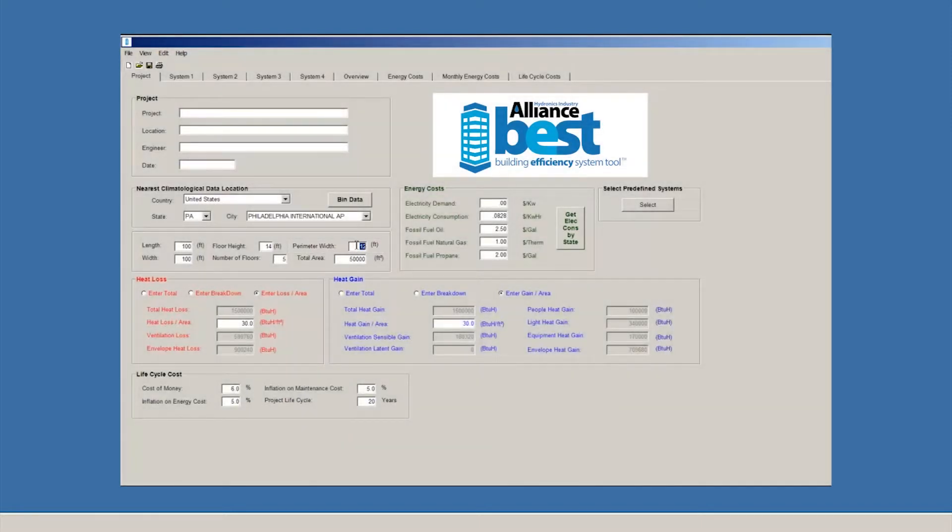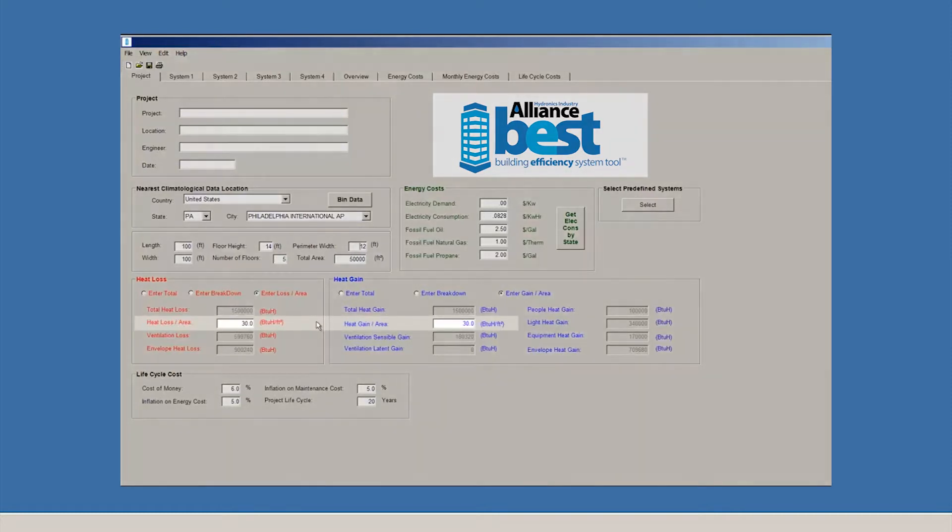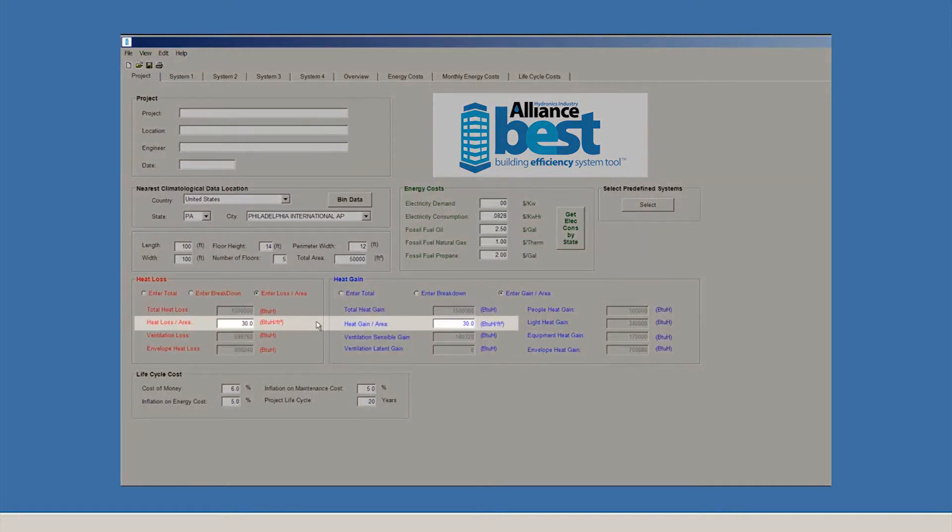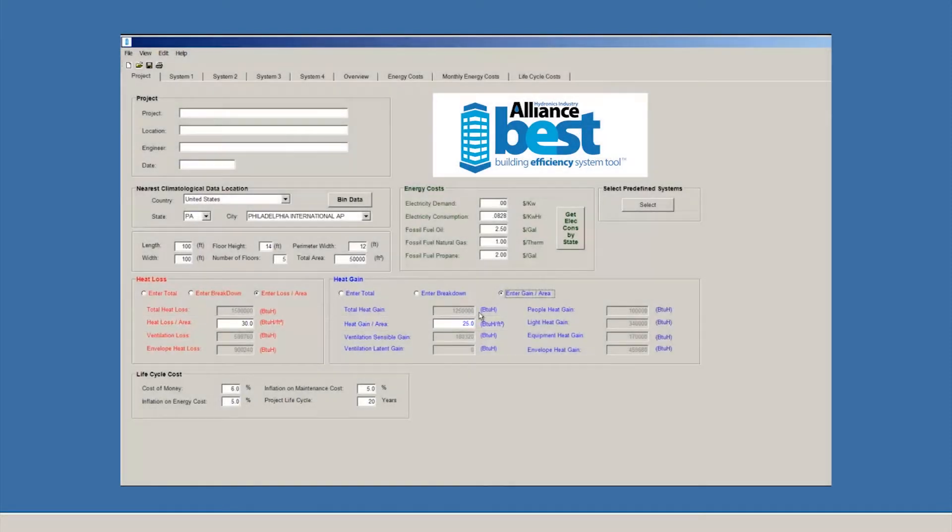For our example, we've entered default values for nearly every parameter. If you don't want to use the defaults, they're easy to override. For example, the default value for loads is 30 BTUs per square foot of heating and cooling. Let's override it and put 25 as the value for cooling. The calculations will adjust accordingly.